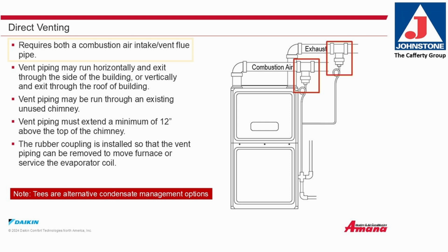Direct venting requires both a combustion air intake vent and a flue pipe. Vent piping may be run horizontally and exit through the side of the building, or vertically and exit through the roof of the building. Vent piping may be run through an existing unused chimney. Vent piping must extend a minimum of 12 inches above the top of the chimney. The rubber coupling is installed so that the vent piping can be removed to move the furnace and service the evaporator coil. Y's and T's are alternative condensate management options.